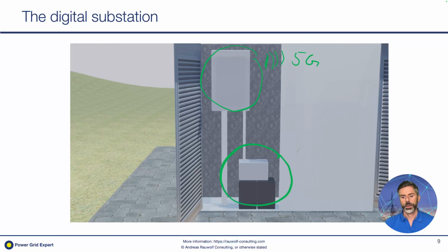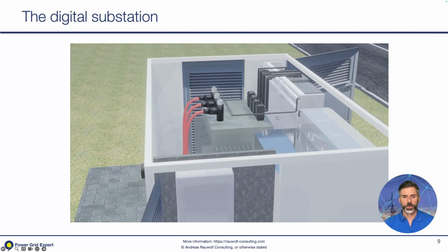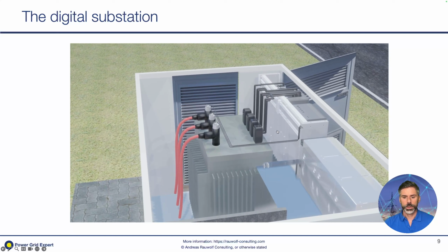And of course, we have the UPS system here. Of course, if we want to control the whole substation in case of a blackout, which is one of the main purposes for all that technology here, we need a UPS system that stores enough energy to keep the substation connected to the SCADA and also delivers enough energy to drive the motor switches of the medium voltage switchgear. We continue our travel and we're having a look at the transformer, and here there is the last difference when we talk about the digital secondary transformer station.